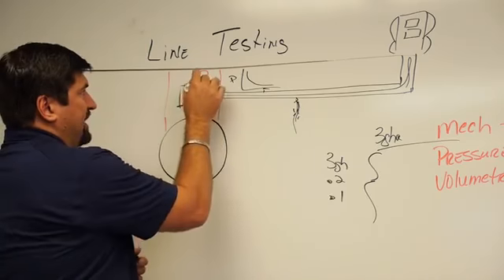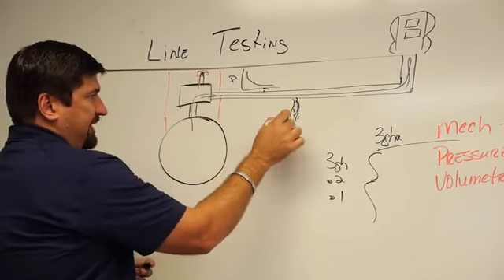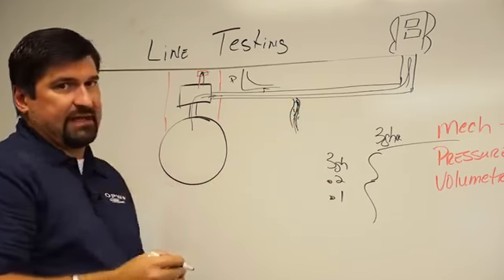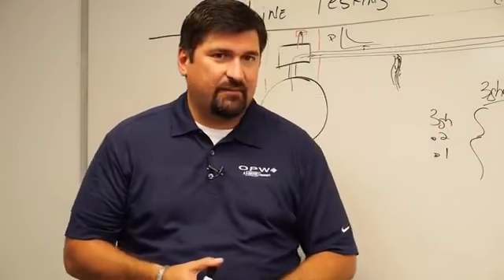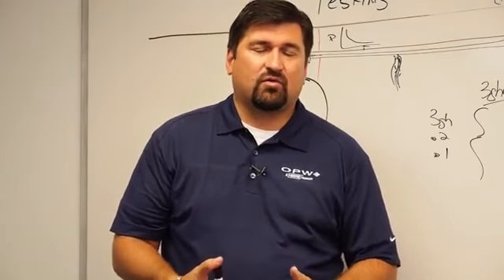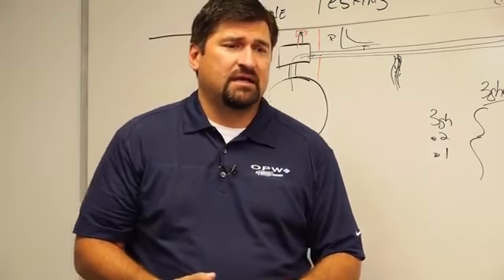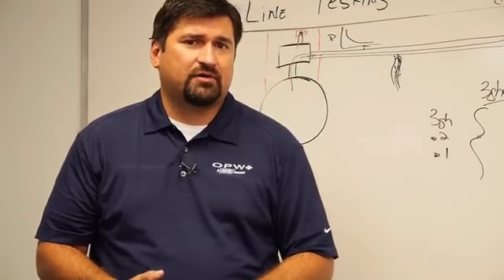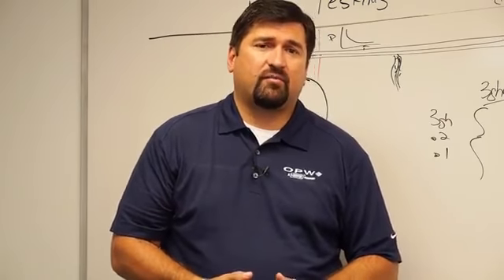In a volumetric scenario, what you're looking at is measuring the amount of volume flow through a sensor, and we're metering out how much product is leaving that pipe. Both pressurized and volumetric line tests meet the state and local requirement for a 3 gallon per hour line test, but they also meet your 0.2 monthly monitoring as well as your annual monitoring for the 0.1 test.